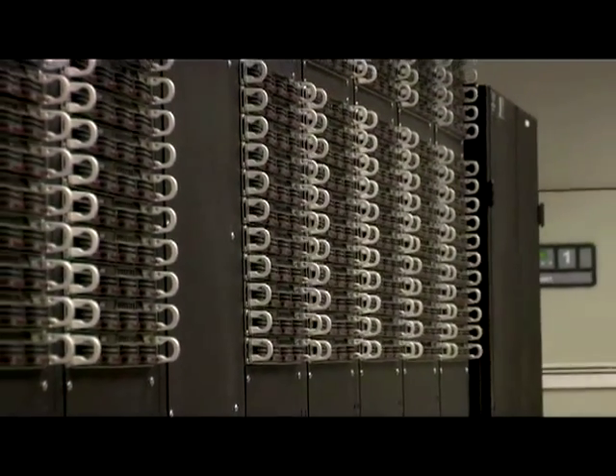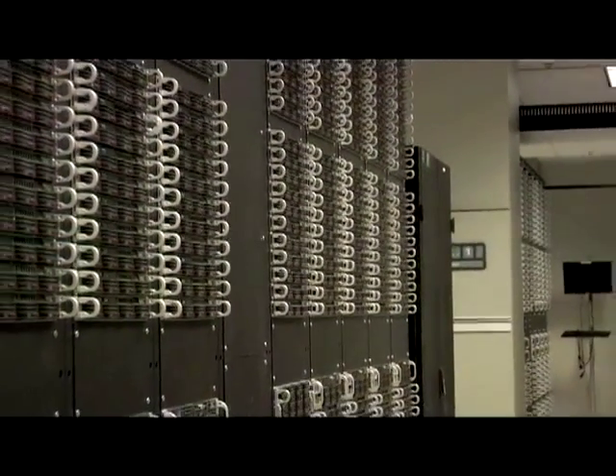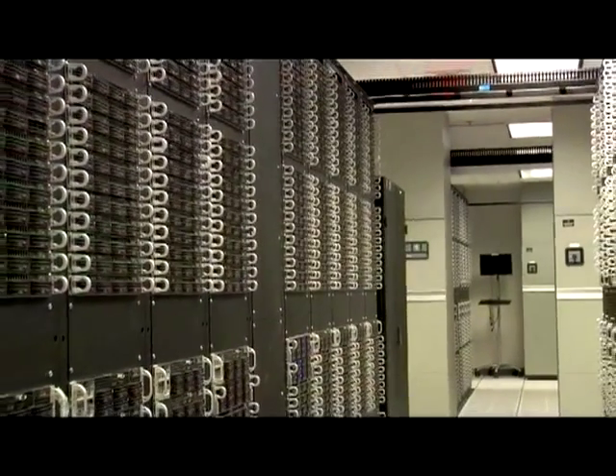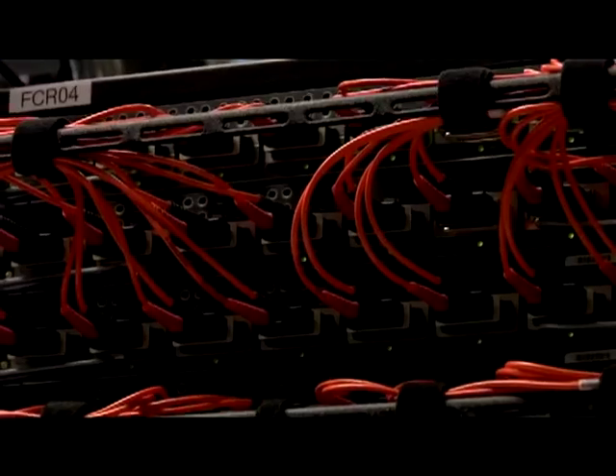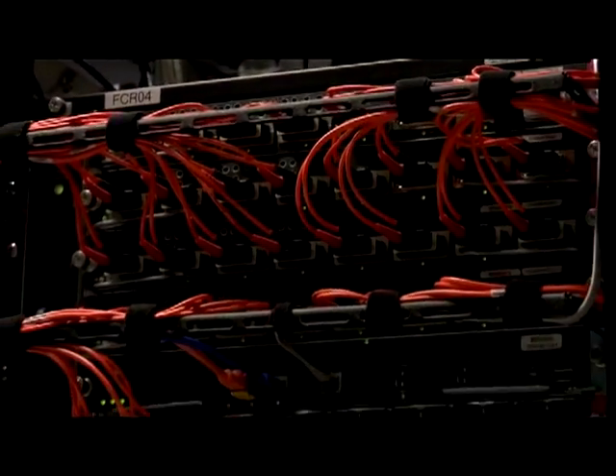It's amazing, it sounds like it's really working hard. How efficient is this particular data center? We have to go out of our way to be as efficient as possible on power. We're running about 250 watts per square foot here with 44 servers in a rack, so we have to maximize all the efficiencies. We utilize high efficiency power supplies, low voltage processors, low voltage RAM, trying to mitigate electricity usage as much as we possibly can.